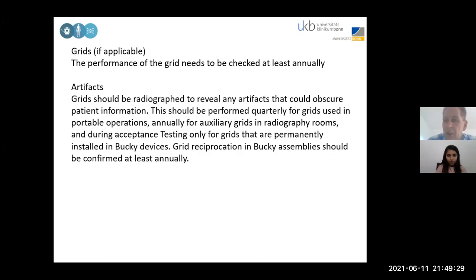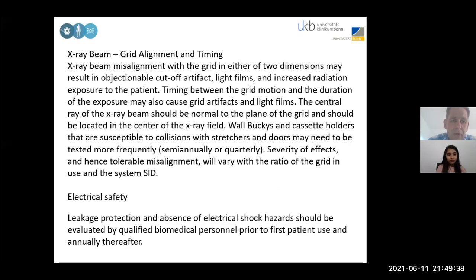If you still have a machine which has grids, you should see whether the grid makes artifacts or not. I would recommend checking that annually, and the grid alignment. And at the end, the electrical safety, so that the machine is really safe and no cabling is open. I already had a machine where I got a shortcut while touching one of the sensors. So that happens. But this is not really quality control; X-ray devices are also electrical devices. So this was the part on quality control.